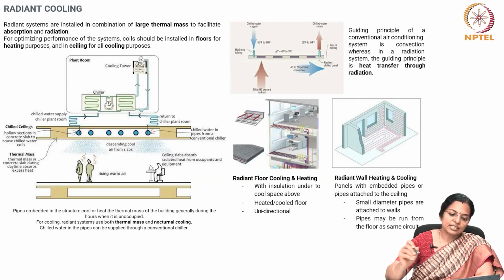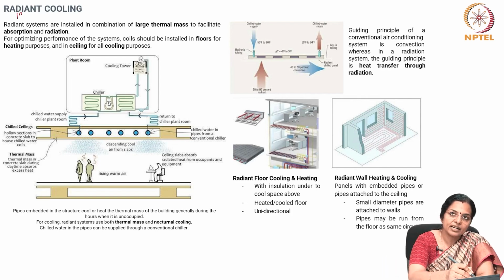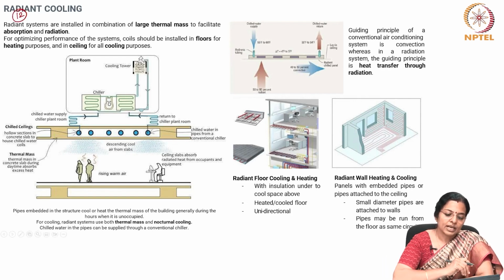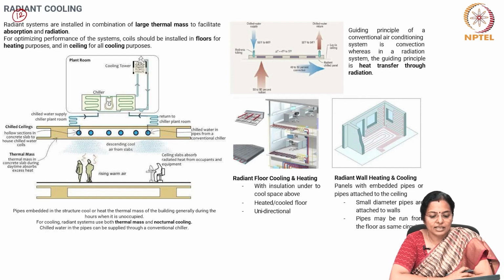Well, the next strategy that we will look at is the radiant cooling system. The radiant systems are installed in combination of large thermal mass to facilitate absorption and radiation. They are also used for optimizing performance of the systems, and these coils should be installed in floors or in ceilings. For heating purpose it is used in floors, and it is used in ceilings for all the cooling purposes.